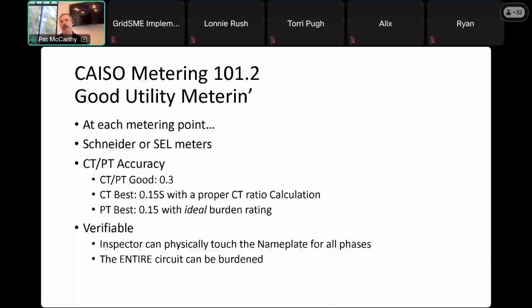To give you an example, CAISO requires a meter that has a 0.2 accuracy class, which translates to a maximum error tolerance for the meter's measurements of 0.2%. That was the highest accuracy you could get at the time. But there is now a 0.1 class, which is twice as accurate. That 0.1 class is certainly available from both Schneider Electric and Schweitzer, the two meters that I have recommended. There might be some other folks now representing that accuracy class, I don't know, but I also don't recommend using many other meters. We can talk about that later if you want to.